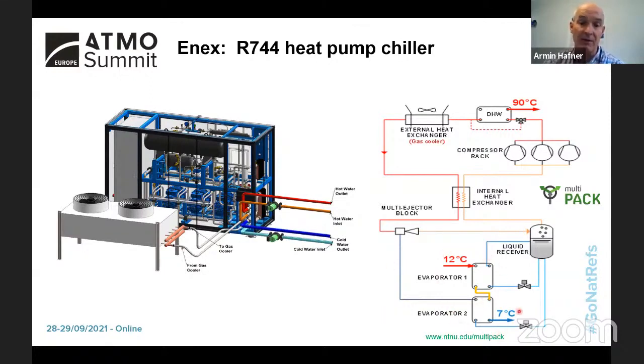What is very unique when you introduce the ejector is a small pumping device operated by the expansion work, and in this case it is utilized to create two temperature levels, elevate the suction of the compressor, and improve the energy efficiency. So it means you can deliver 7-degree water in this case and evaporate at an even higher temperature, because the ejector is the booster in this system to bring up the level for the suction for the compressor, which improves the energy efficiency a lot. So that's a very smart utilization of the ejector for these kinds of systems.